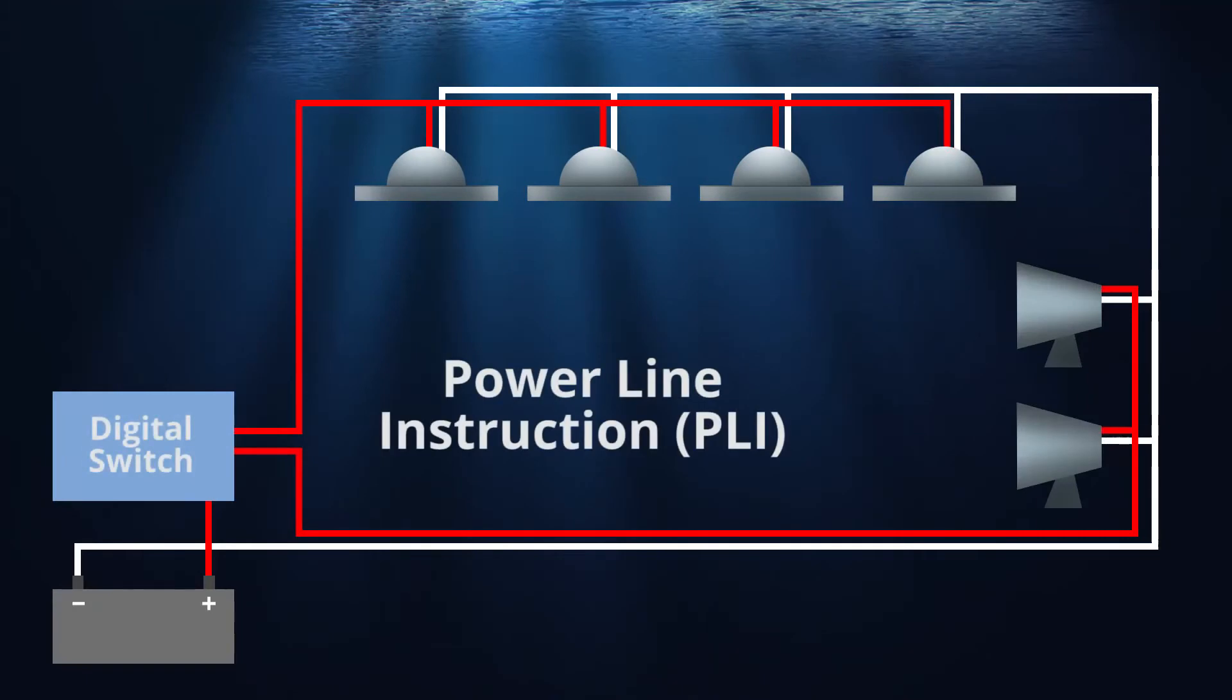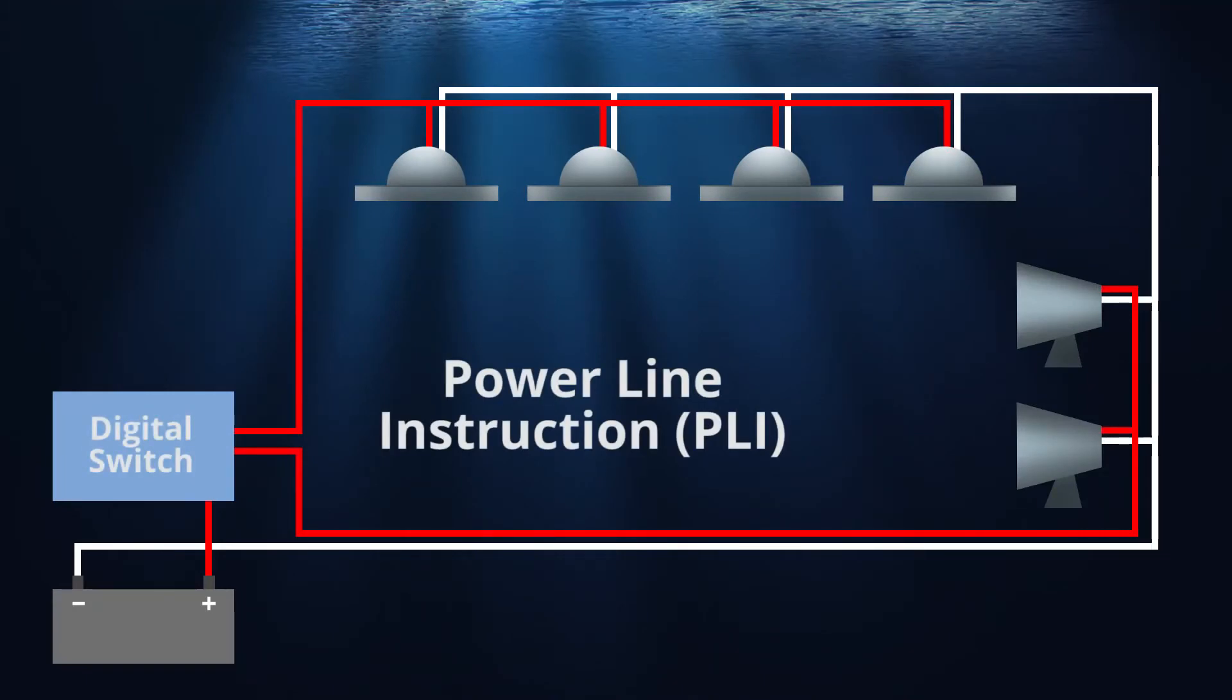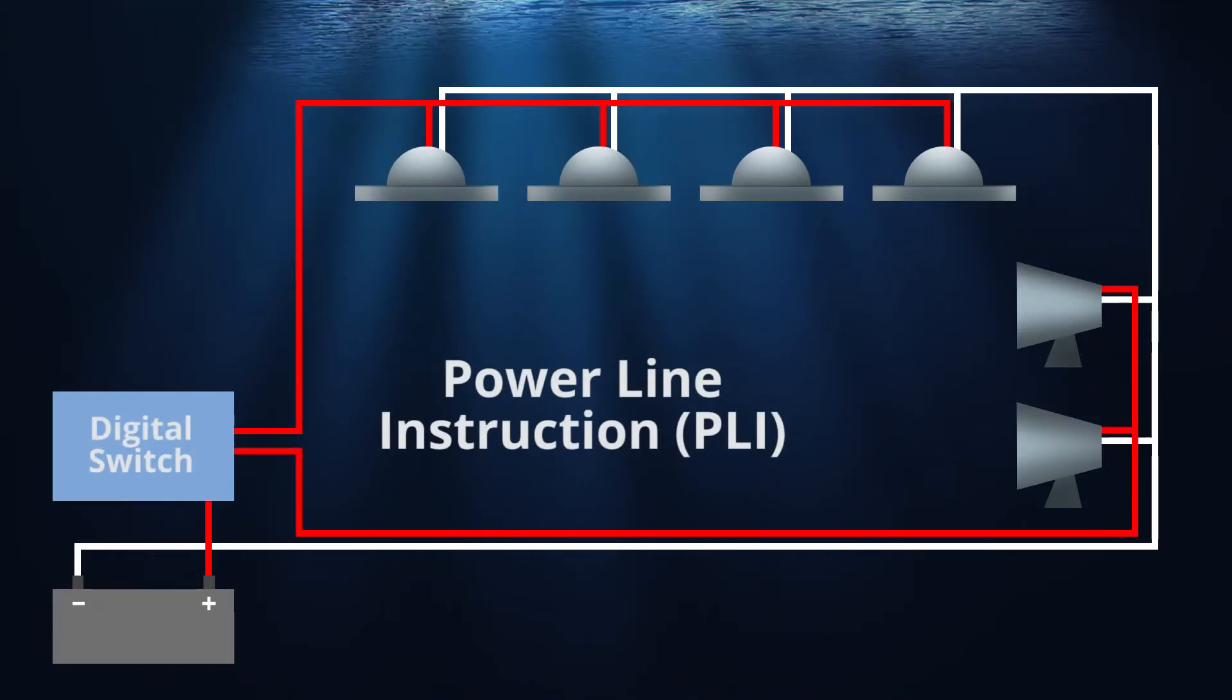With Lumitech's power line instruction technology and a compatible digital switching system, lighting controls can be initiated anywhere onboard the vessel. The commands are converted to a 32-bit message and sent to the light over the power wires. Specialized circuitry in the light initiates a 2-bit error correction on the incoming message and then processes and executes the signal.